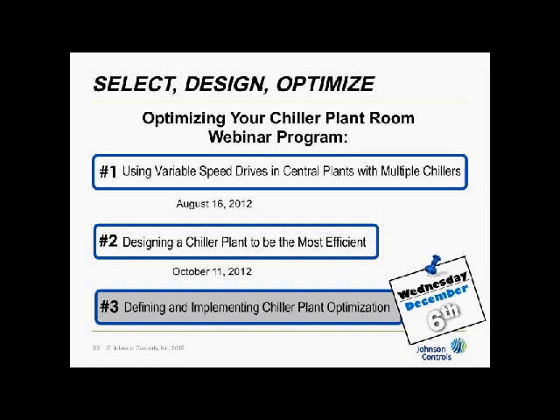So when your whole building is down to 80% load, I'd be at 80% flow on the condenser water pumps and 80% speed on my tower fan. The tower fan would remain there until I got to minimum condenser water temperature. I can't go below on the chiller, be that 50 or 55, and then it would start slowing down again. So it has a slow down with load down to 80, and then once you hit 55, it slows down to whatever speed it's got to maintain that 55.